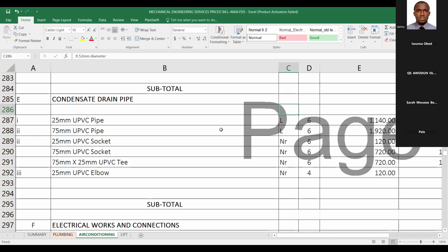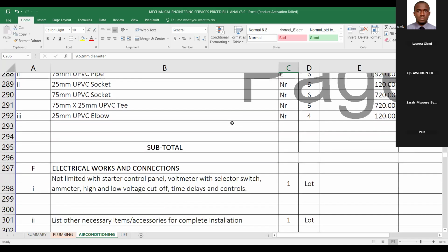You can't compare a single unit with just a capacity of 1.5 horsepower at the rate of 3.61 kilowatts in this case, and now compare it with a capacity of 11.5 kilowatts, and you still want to use the same cable. No, it's not possible. In this case, you'll be using 4 mm flexible cable, 4 core flexible, 4 mm by 4 core flexible cable will be used in this case.